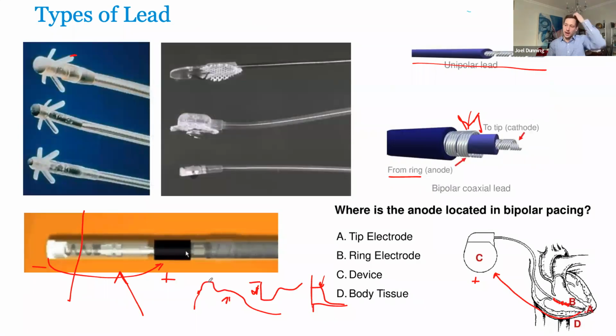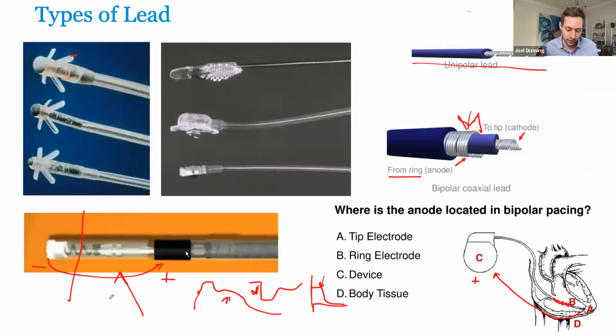Jared, that was a really good point, what you mentioned as far as capture. One thing that a physician showed me a number of years back that I thought was pretty cool, and I like to use for implants, is just quickly going unipolar with the cables as you're implanting a lead, just to assess whether or not the unipolar impedance is higher than the bipolar impedance. So in general, your unipolar impedance through the electrical system should be lower. But if you've perfed into the myocardium, what you may find is that your unipolar impedance, because you're outside of the heart itself, is higher.